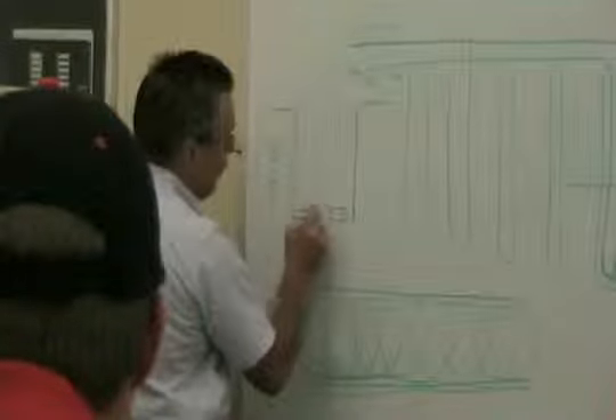Whoa. Right down in Texas, on the Colorado River, they actually had the pipe go down into the river itself, and had to have a screen on the end to keep the trash out. But in fact, that was one of the problems with the water flow. Every now and then, that screen would fill in. Yeah. Now, the third method is generally in a horizontal ditch. So I've got a ditch that's generally 5 foot deep to 7 foot deep, and this slinky is laying in that ditch.